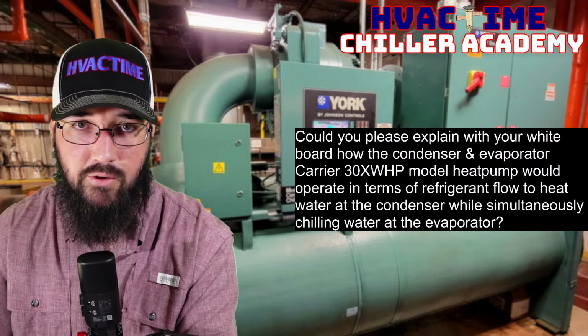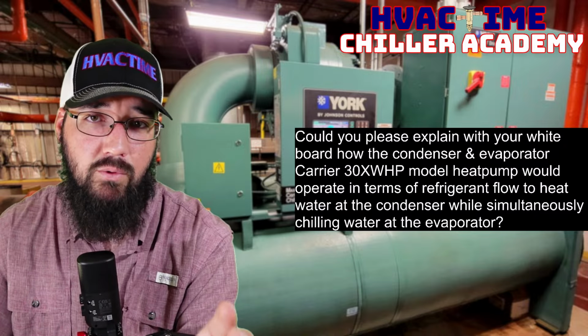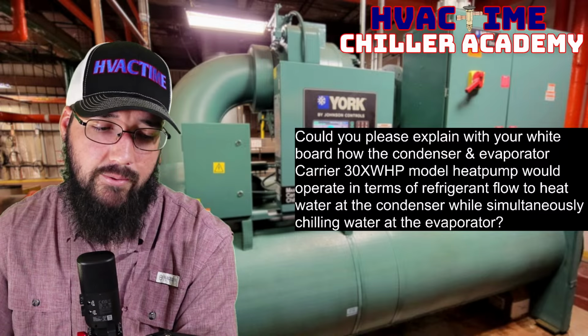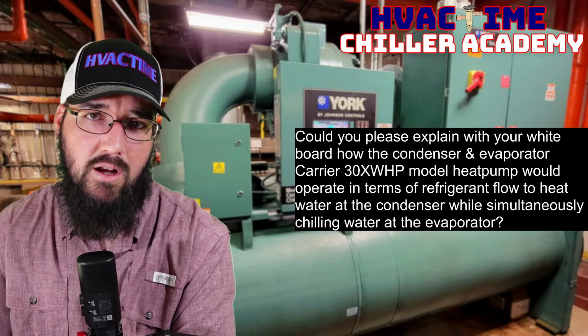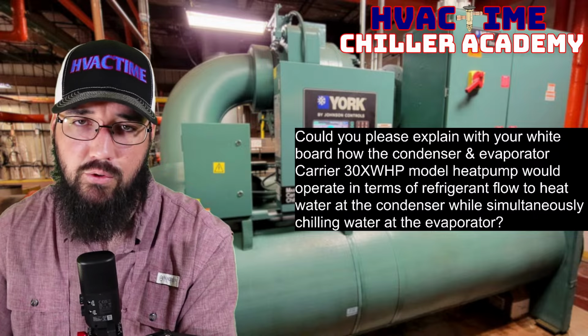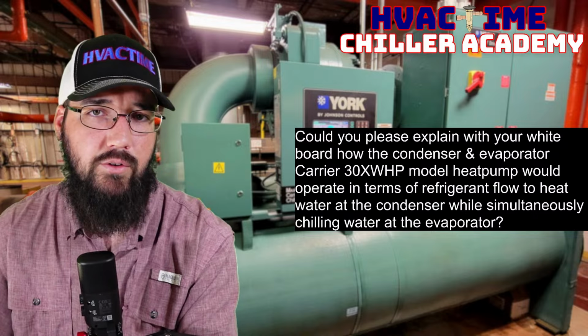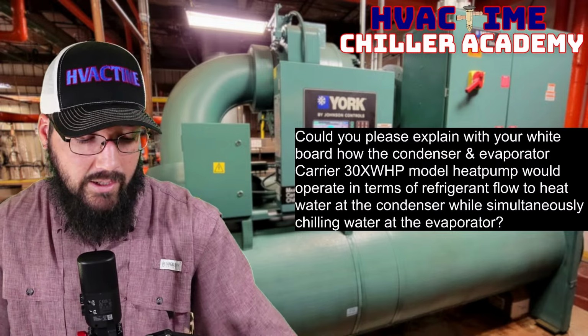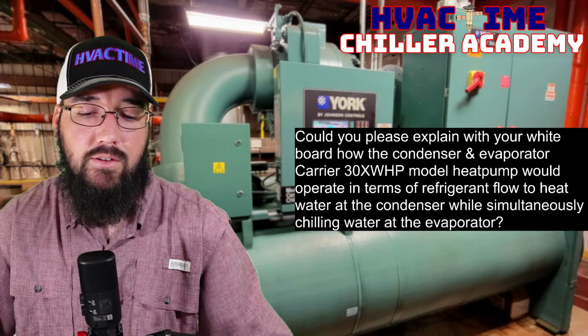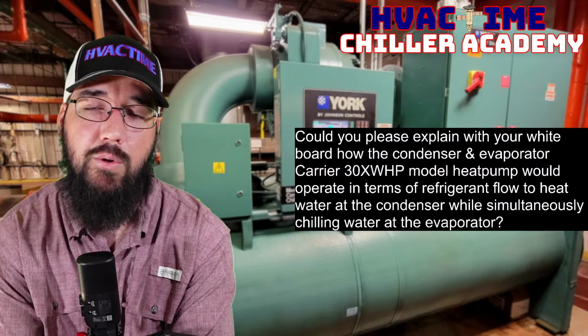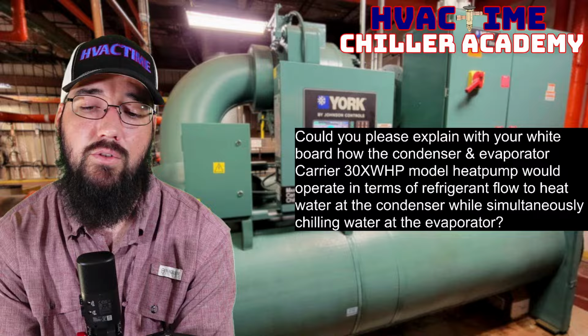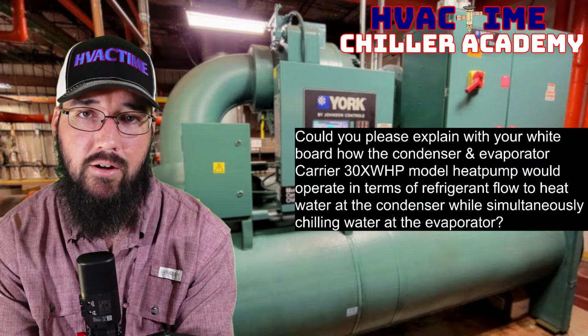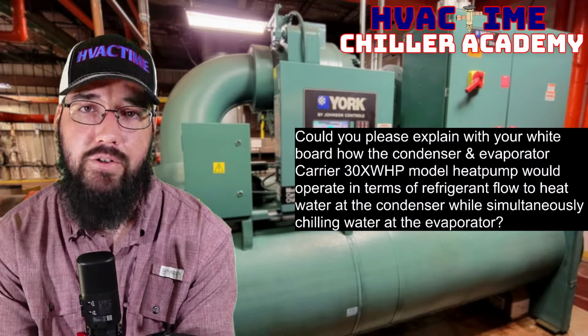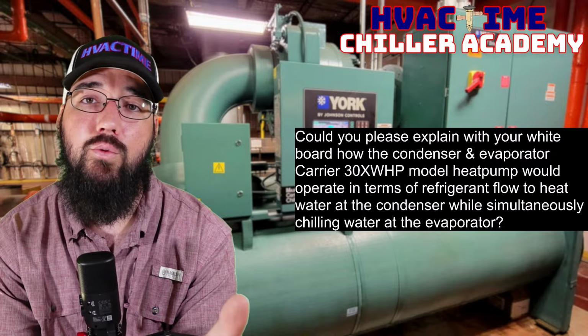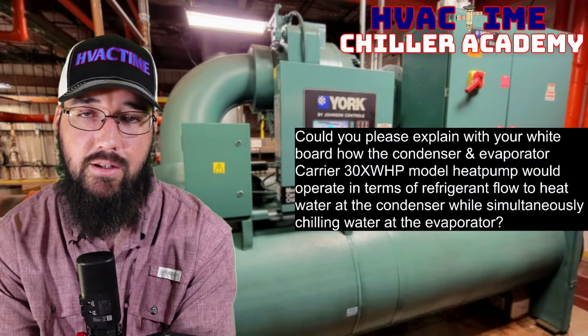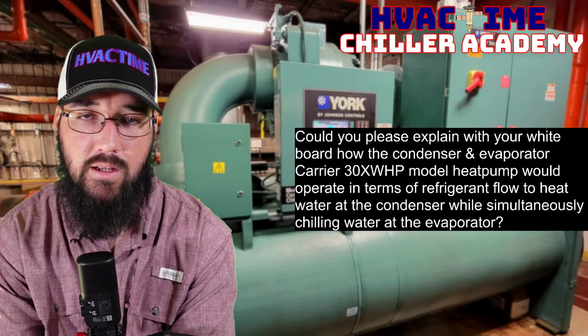at any other point. Like I said, the only thing in that circuit that I don't recognize is going to be those little boxes down at the bottom of the condenser. I'd have to do some research to see, okay, what are those? What is their purpose? That's not something I'm familiar with. But beyond that, it's still the same chiller in the end. It's doing all the same things. It's just designed to operate at a much higher compression ratio, much higher condenser water temperatures in order to achieve the heat pump functionality. That is its ultimate baseline goal.